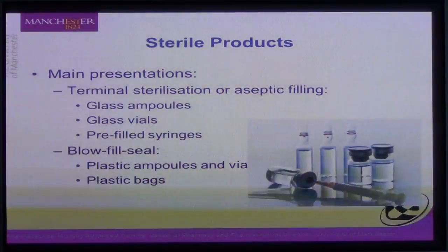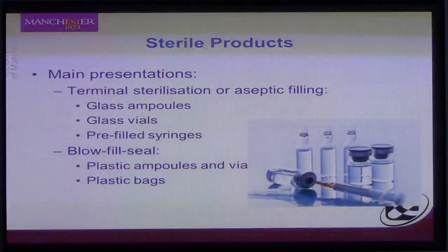There are different presentations. Terminally sterilised or aseptically filled products tend to be made in glass ampoules, glass vials, or as pre-filled syringes. There is an alternative method called blow-fill-seal, which straddles the boundary but should always be classed as an aseptic filling process. Blow-fill-seal is used for manufacturing plastic ampoules and vials or putting product into plastic bags, and it reduces risk somewhat by sealing within the filling machine itself.